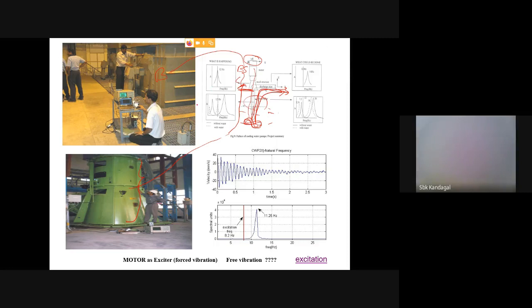The idea here is, whenever it is operating at something like 720 RPM, we can see that there are a lot of resonance and vibration problems. We were supposed to find out the reasons why it vibrates so much, and then try to control that.